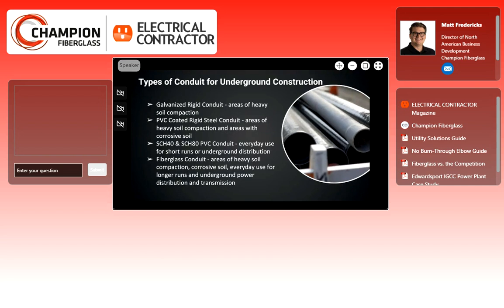If you were in an area that had quite caustic soil but also heavy soil compaction, rather than taping a whole piece of galvanized rigid conduit with anti-corrosive tape, you could use something like PVC-coated rigid steel conduit.